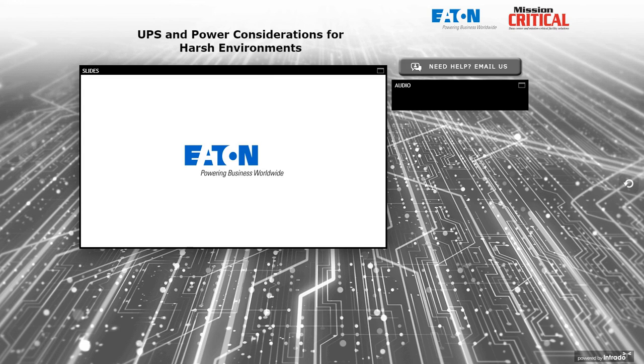There are several different ways of addressing these, and some requirements like the IBC Zone 4 requires that the UPS remain in place during a seismic event. It doesn't necessarily have to remain operational, whereas OSHPD, which is originally a hospital-related seismic requirement, started in California and is becoming more and more widespread. It requires that the machine remain functional during and after a seismic event.